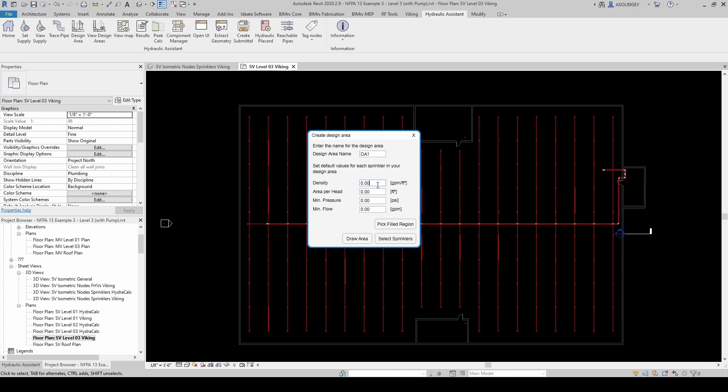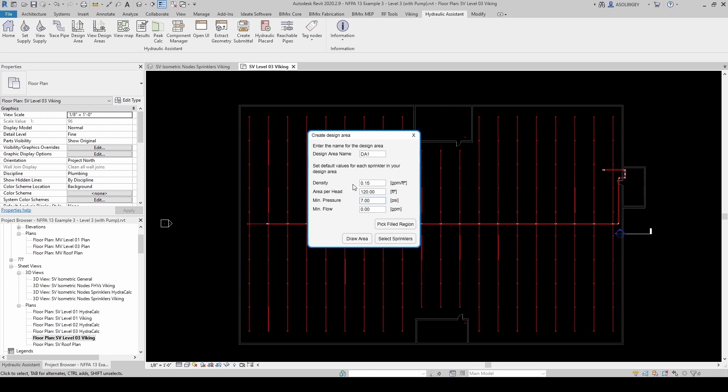The density, since this is Ordinary Hazard Group 1, is going to be 0.15 GPM per square foot. Maximum area per head is going to be 120 square feet. The minimum pressure is going to be 7 PSI per NFPA 13. And then this minimum flow here is going to be calculated either based on the 7 PSI minimum per NFPA 13, or based on the density times the area per head. So whatever is largest, that's what Viking is going to use here.